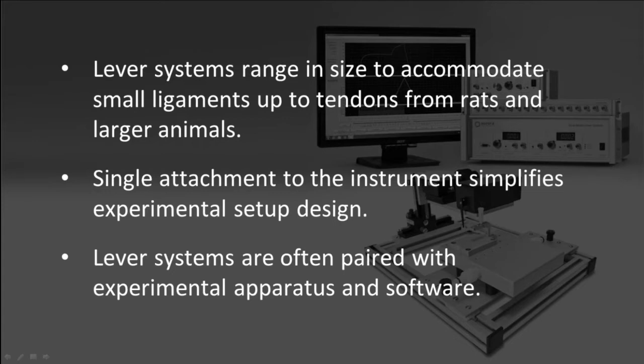So while the lever system is clearly versatile enough to work with a wide variety of tissue types and samples, it's not a complete replacement for a material testing system. It works very well with certain samples, but it's not designed to do everything. The unit is an active control system, so all samples have to have some degree of compliance and elasticity. So it's not suitable for loading in compression, or applying tensile loading to extremely stiff materials like bone.